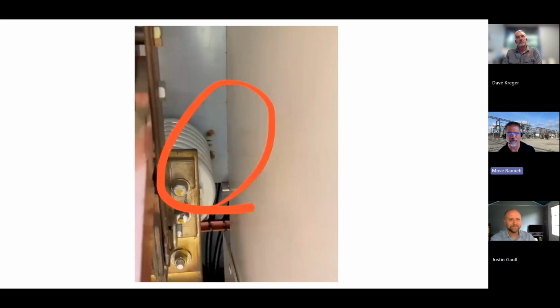Yeah, this is another great example of environmental factors, and a great example of the importance of maintenance. We do electrical testing - we test insulation resistance and contact resistance and cables and meters - but do we check the heaters? This is a WLI style switch that's outdoors, and in the spring and fall, when the temperatures swing radically, condensation can occur. When it does, the condensation gets on the insulator with a little bit of dirt, and you start getting these what look like little cigarette burns at the base of the insulator. Those are little arc flashes - little partial discharges that are burning the paint on that particular insulator. Once again, left unchecked and unmaintained, eventually this switch will fail and could possibly expose people to that arc flash energy when it does.